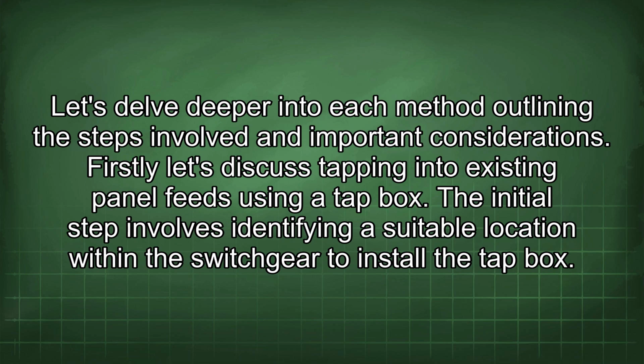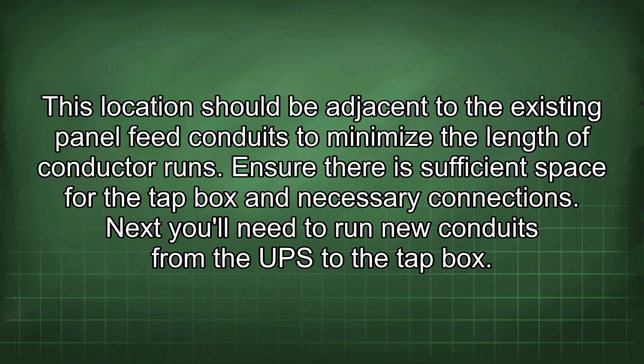Firstly, let's discuss tapping into existing panel feeds using a tap box. The initial step involves identifying a suitable location within the switchgear to install the tap box. This location should be adjacent to the existing panel feed conduits to minimize the length of conductor runs. Ensure there is sufficient space for the tap box and necessary connections.